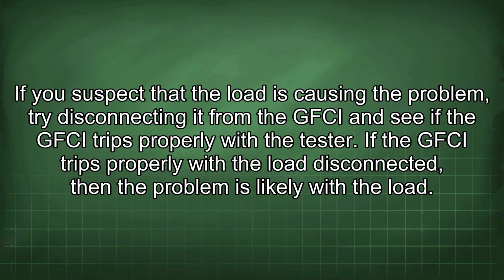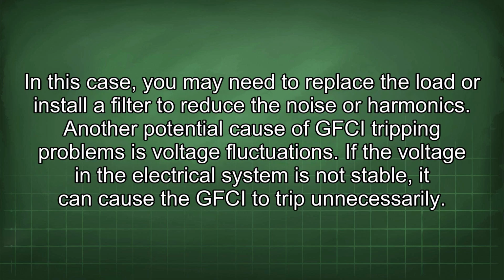If you suspect that the load is causing the problem, try disconnecting it from the GFCI and see if the GFCI trips properly with the tester. If the GFCI trips properly with the load disconnected, then the problem is likely with the load. In this case, you may need to replace the load or install a filter to reduce the noise or harmonics.